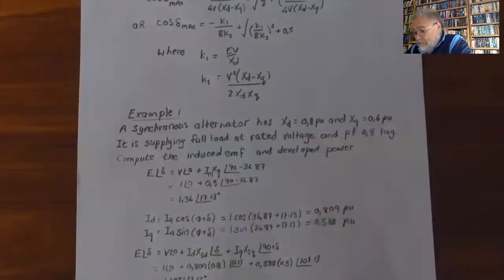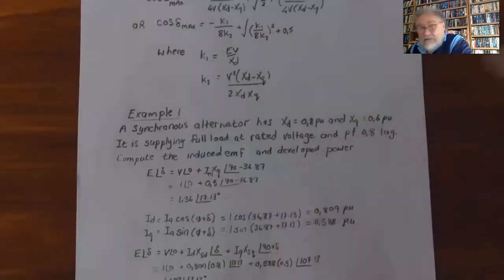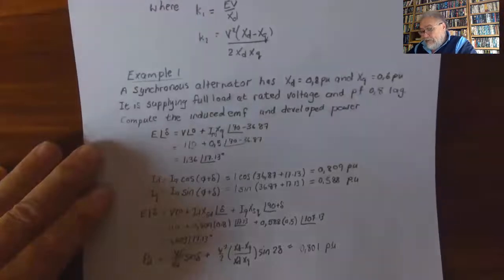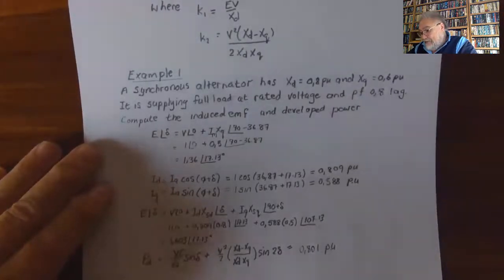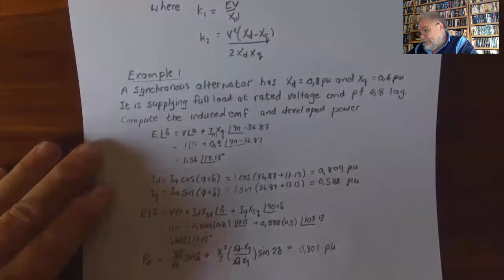Now E = V + Id·Xsd∠δ + Iq·Xsq∠(90 + δ), giving 1.603∠17.13°. If this angle matches the earlier calculated angle, the calculation is correct. The developed power, working in per unit, is: P = VE/Xd · sin(δ) + V²/2 · (Xd − Xq)/(Xd·Xq) · sin(2δ), which gives 0.801 per unit.